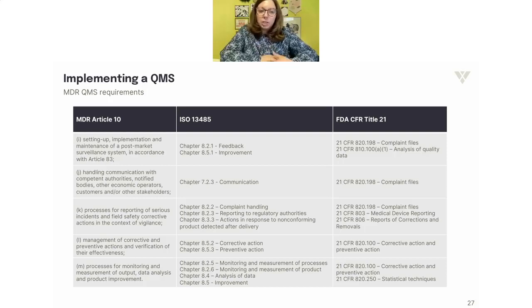So the next one is handling communication with competent authorities and notified bodies. Obviously, this is very specific to the EU. Now, ISO does have 7.2.3 regarding communication. And same thing from an FDA standpoint, there are communication requirements in 820.198 for complaint files. But again, this is very specific to the EU, an area where you're going to expect to have to update your QMS to meet that.